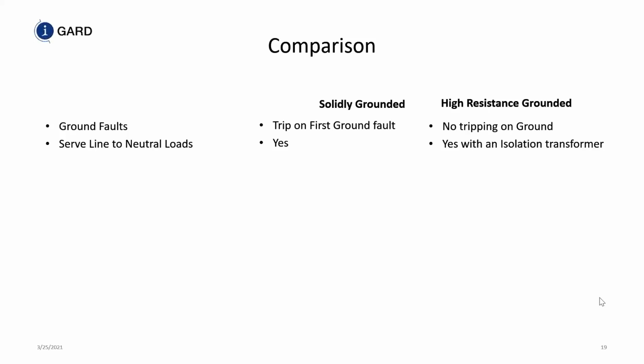And what ends up happening is you end up with a safer system, primarily because your electricians who were exposed to the three-phase bolted fault current when changing the ballast of a 480 volt system from a 2000 kVA transformer, and we saw that current to be 48 kA, now have the bolted fault current coming from a 112 kVA transformer. So you'll find that you end up with much less incident energy where your electricians are going to be doing most of their work in isolating or changing ballast. For safety, they're both safe. No one is going to tell you that a solidly grounded system is unsafe.